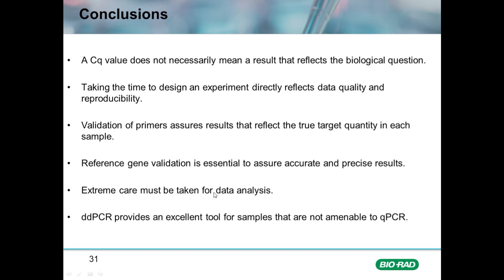Extreme care should be taken for data analysis. I personally don't recommend Excel spreadsheets for calculations — they are fraught with the potential of formula propagation errors and copy-paste errors, especially in larger studies that require multiple plates for analysis. CFX Maestro from BioRad permits the data to remain within the software for multi-plate analysis and clean data output.